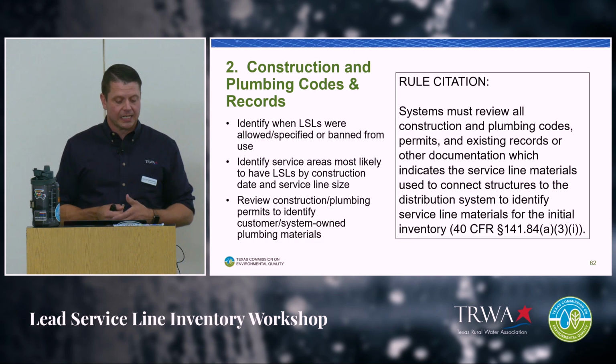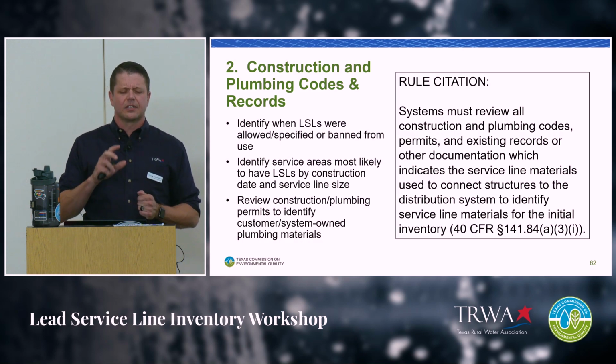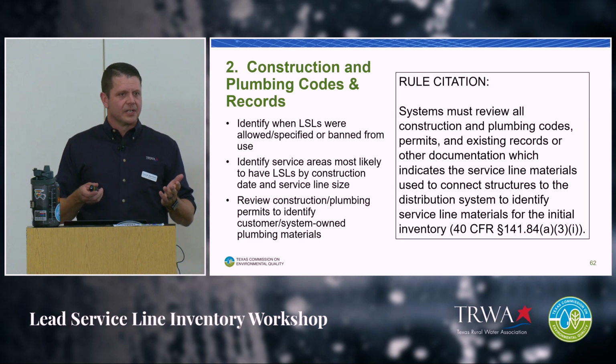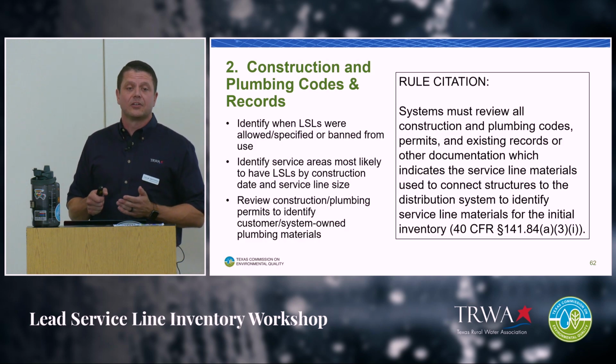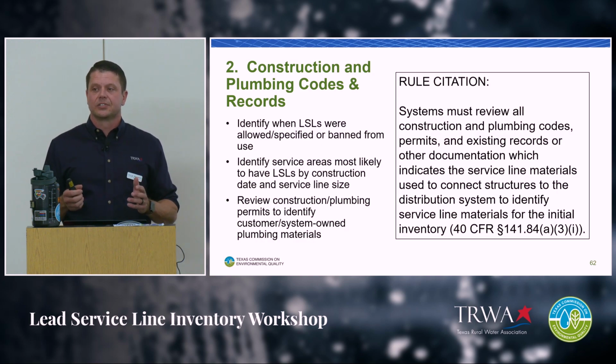Identify areas that are most likely to have lead service by construction dates or even construction of line sizes. And I say that because at a certain point, we weren't even allowed to put in a smaller line, less than 2 inch. So if you have certain sections of your system that say 1.5 inches, you can almost date them back to a particular time, maybe that could be more highly susceptible for lead lines. Review construction and plumbing permits to identify customers and system-owned plumbing materials.